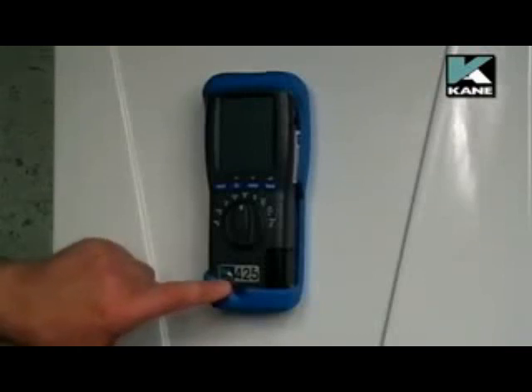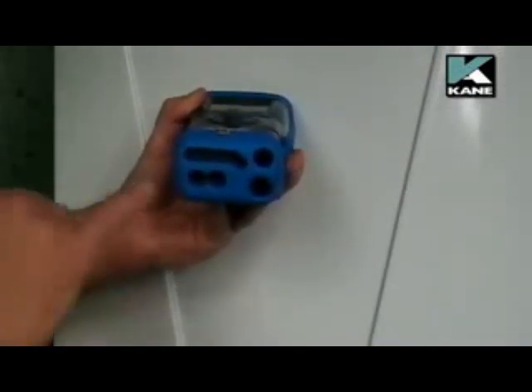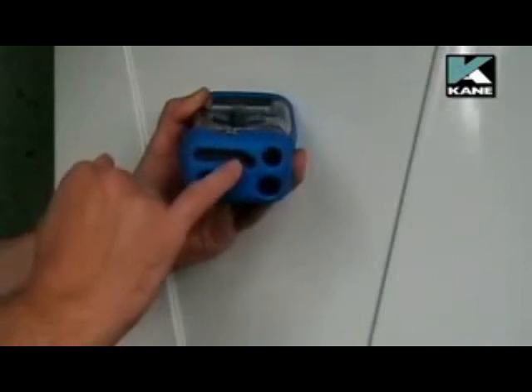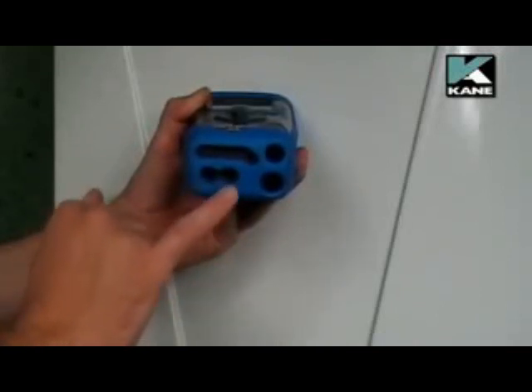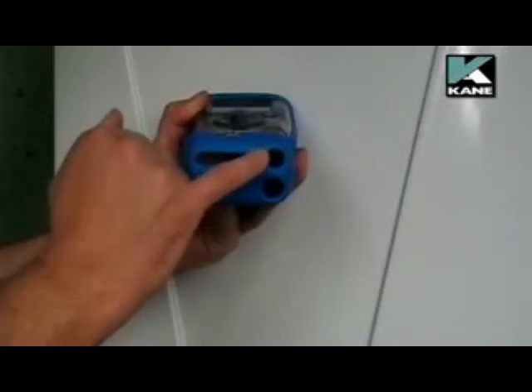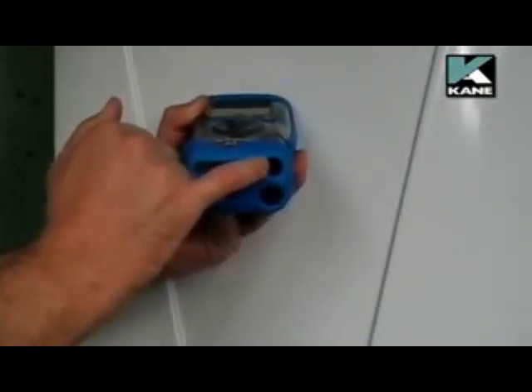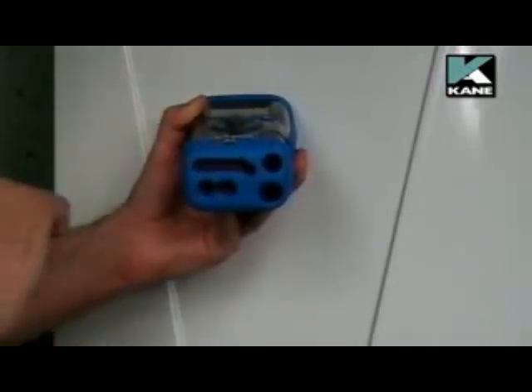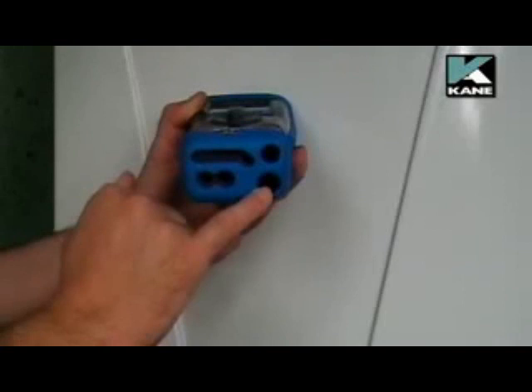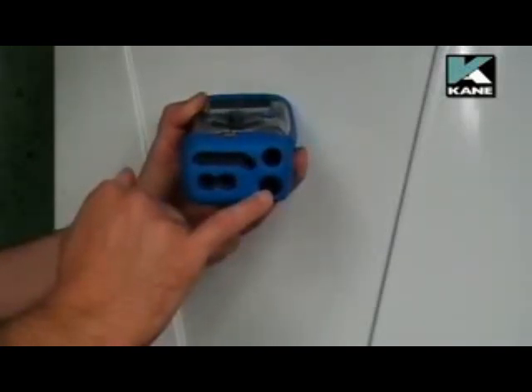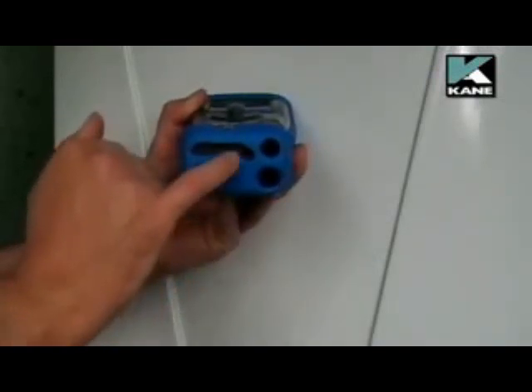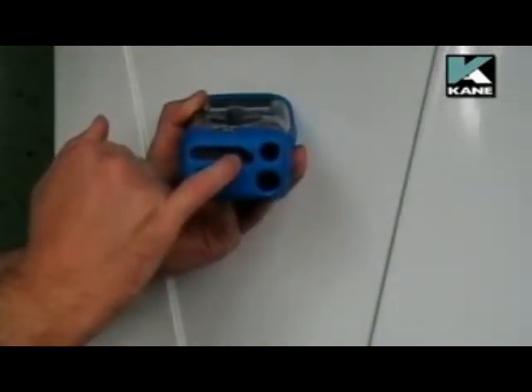Also on the front of the analyzer is a battery charging indicator, which will be orange when it's charging. If we look at the connections on the bottom of the analyzer, you've got 2 connections for temperature. Now these are T1 and T2. You've got 2 connections for pressure, P1 and P2. Here is the connection for the sampling hose, so that's going to connect to the bottom of the water trap. Here we have the rubber bung, which is the drain plug for the water trap. And finally we've got a connection here for the charger unit. Now that can either be used with a 240 volt charger or with a 12 volt charger.